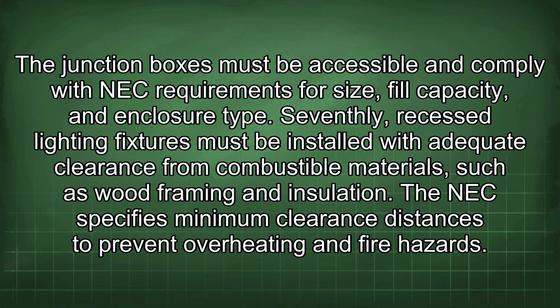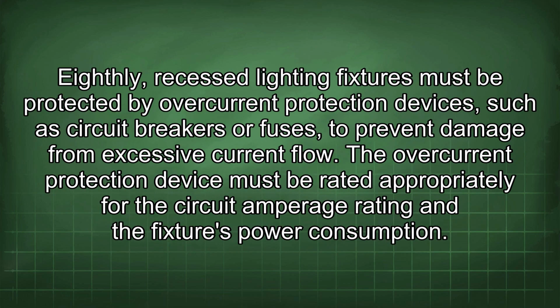Seventhly, recessed lighting fixtures must be installed with adequate clearance from combustible materials such as wood framing and insulation. The NEC specifies minimum clearance distances to prevent overheating and fire hazards. Eighthly, recessed lighting fixtures must be protected by overcurrent protection devices such as circuit breakers or fuses to prevent damage from excessive current flow. The overcurrent protection device must be rated appropriately for the circuit amperage rating and the fixture's power consumption.